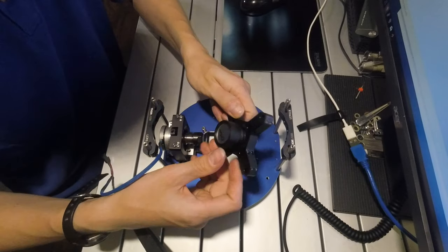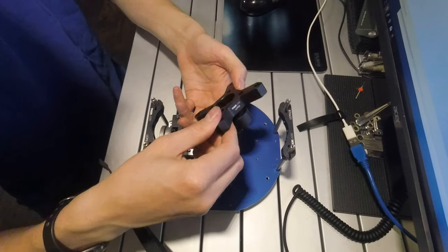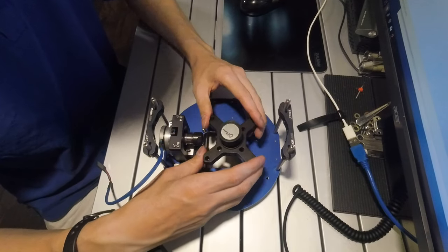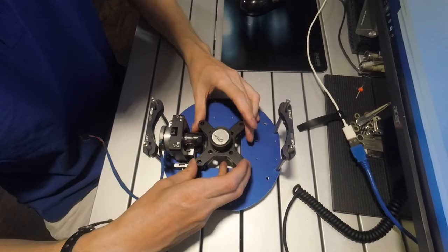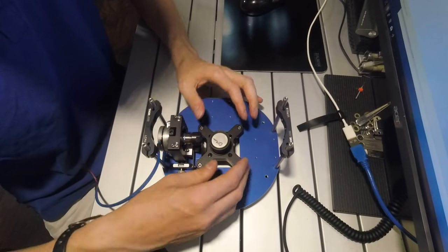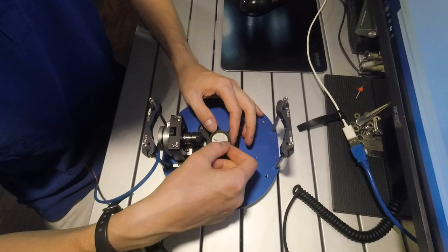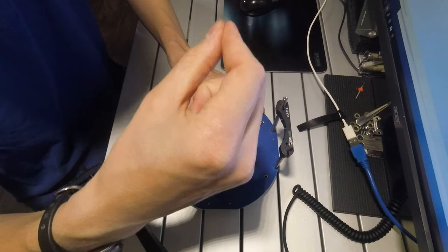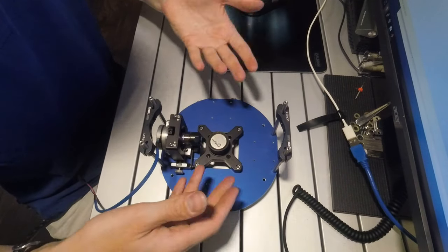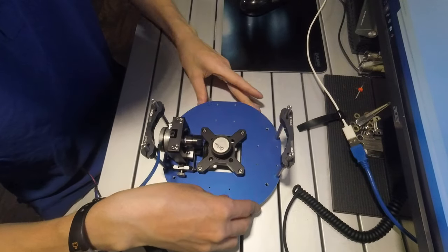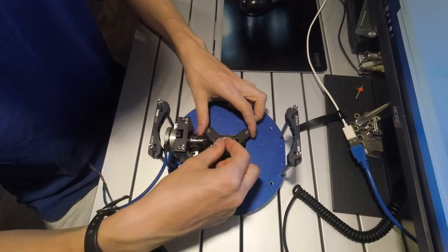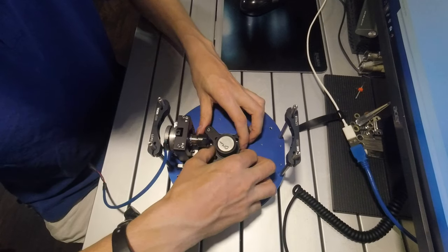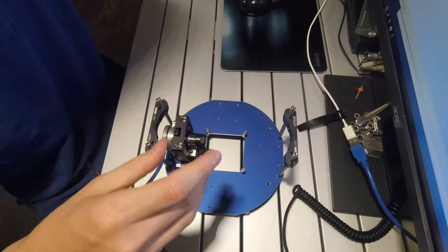Now the collimator will be used for future x-ray fluorescence analysis by installing a cadmium zinc telluride or other energy sensitive detectors. When this would be installed this would basically restrict the x-ray beam with a 0.4 millimeter aperture so you just have a needle fine beam coming down right in the center of the sensor. So you could take an x-ray of material or object, adjust it to wherever what you want to analyze is in the center of the sensor, then insert the collimator and put the x-ray beam onto that and detect x-ray fluorescence for materials analysis.